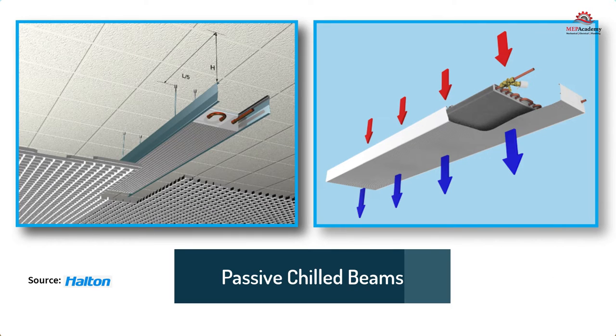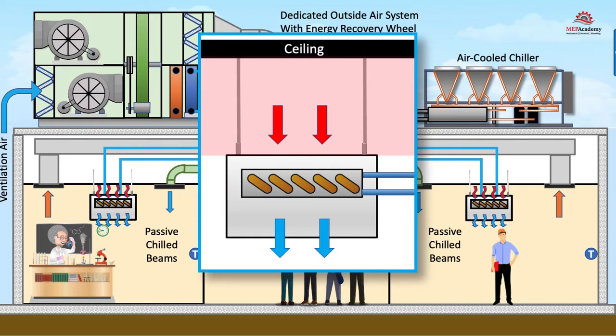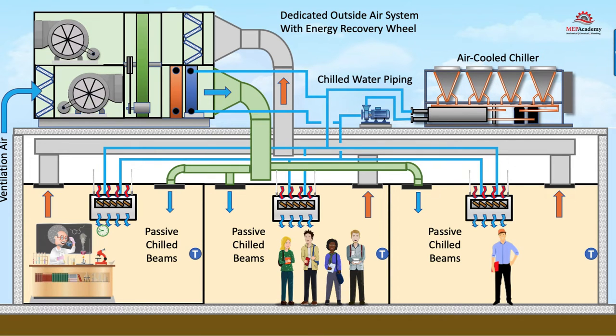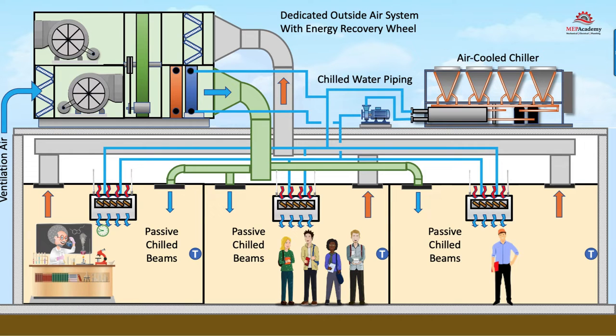A passive chilled beam contains one or two coils in a sheet metal housing suspended from the ceiling. Ventilation air is required for the space, but with passive chilled beams, the ventilation air is delivered directly to the space and not through the chilled beam. The passive chilled beam uses natural convection to cause air circulation — this occurs when the cool air surrounding the coil becomes denser and drops, while the warmer air naturally rises to the ceiling. This occurs without the use of a fan, hence its passive. The key difference between active and passive chilled beams is how ventilation air is delivered to the space and how much cooling can be achieved.